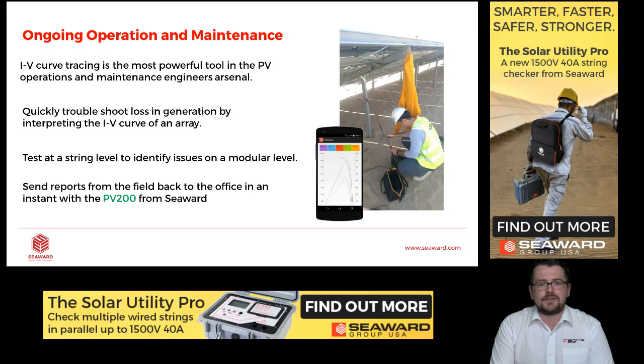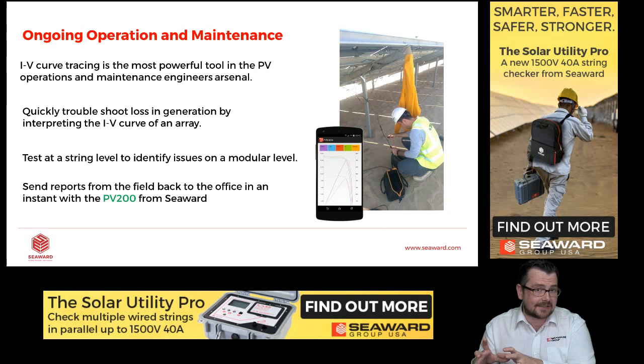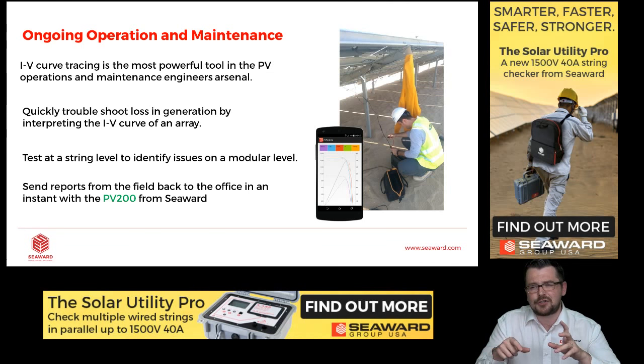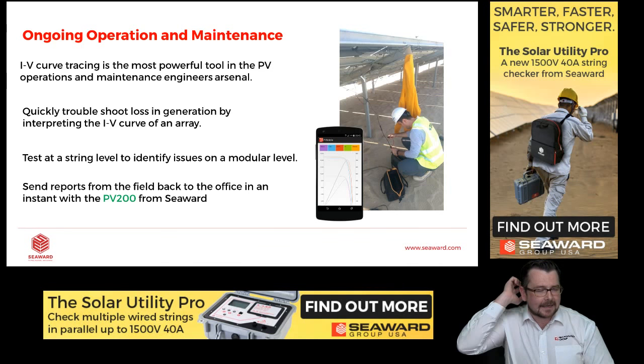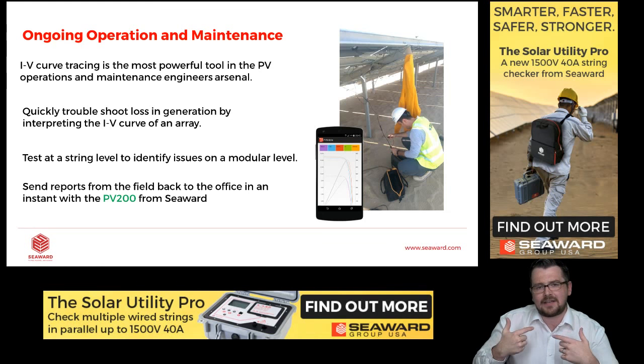Ongoing O&M, operations and maintenance of PV plants, is a great concern. Even when the number of installations drops in your country, there will always be panels and installations that need to be tested and maintained. So IV curve tracing is the most powerful tool we have to diagnose issues. Whereas we can determine issues with VOC, ISC, insulation resistance, that is, open circuit voltage, short circuit current, insulation resistance, the IV curve gives us a bit more in-depth data. So my suggestion would be to test VOC and ISC first, and if they don't line up with your expected values, then pull out the curve tracer.